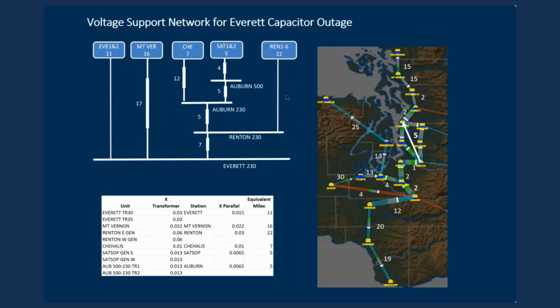Renton is also another generator feeding the system, so we have to model the merging of the path from Renton along with the path from Auburn. So the path from Auburn is 5, the 2 plus 2 plus the 1, to the 230 kV. The distance from the Renton high side bus is 0, so there's no mileage required there. And then to go from Renton to Everett, we've got 7 miles, and that represents the 5 miles of this equivalent circuit. Remember, we built an equivalent circuit of 5 miles, which represents the path around this side, from Renton to Seattle to Linwood, and from Renton to Bellevue to Redmond to Linwood. All of that is 5 miles. So now you're seeing we've got 5 miles from Renton, jumping all the way to Linwood, and another 2 miles, so that gives us 7 miles here.